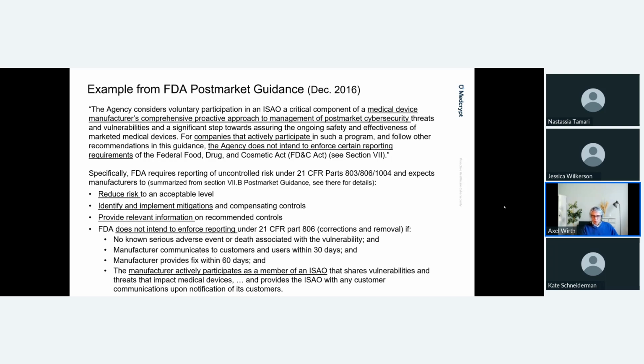base. However, it is also stated in the post-market guidance that the FDA does not intend to enforce reporting under Part 806, meaning correction and removal of devices, if there's no known serious adverse event or death associated with a newly discovered vulnerability, it is communicated to customers and users within 30 days, manufacturers fix it within 60 days, and a manufacturer is an active participant and a member of an ISAO that helps with the sharing of vulnerabilities and facilitates communication and so forth.